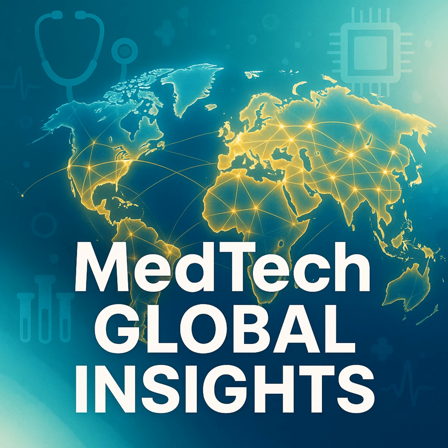Selecting a predicate isn't just about finding a similar product. It's about matching the intended use, technological characteristics, and performance data with forensic precision. This brings us to the second common failure point: insufficient performance testing. Your submission must include a robust body of evidence, including biocompatibility, sterility, software validation, and performance bench testing.